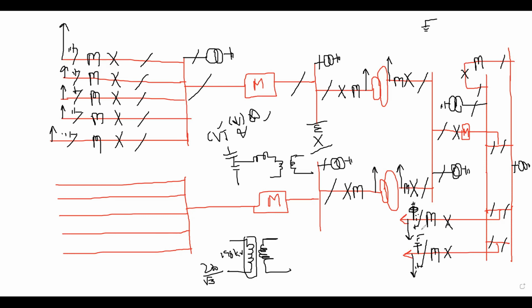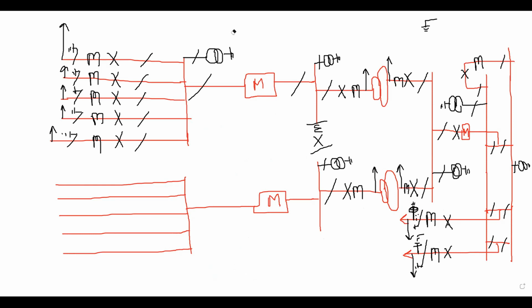And why in some cases CTs are placed on the line side, maybe you can understand or not. I will just clarify this, and I will repeat it in control and protection, just as an example to give an idea. Suppose the breaker is in open condition. Now I close the breaker here, and I don't know that there is some fault here.